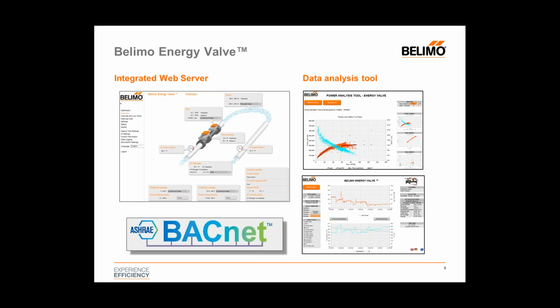Now when a new coil is installed that has a design delta T, but 20, 30 years later, or after a period of time, that coil's heat transfer degrades for various reasons. Dirty coils, damaged coils, various reasons. And that design delta T can no longer be achieved. So there's really no way of understanding what that new design delta T could be. That's where the energy valve comes in so handy.